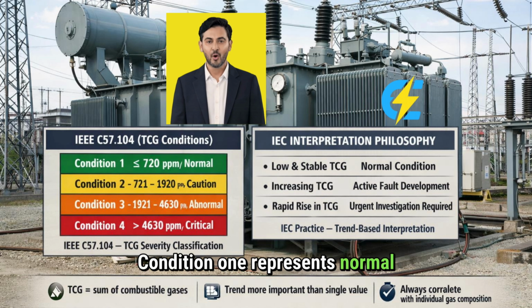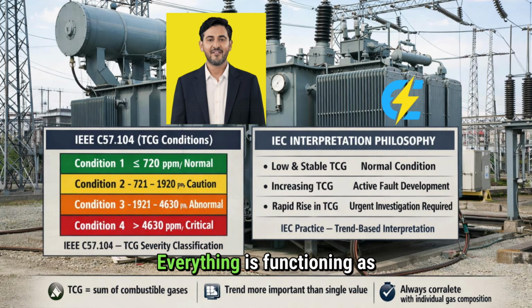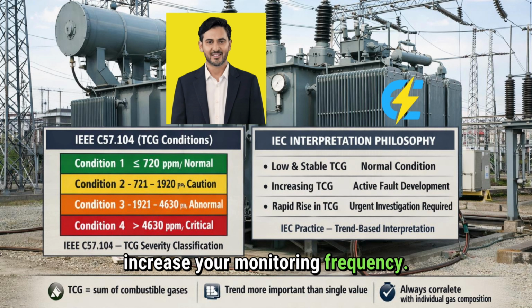Condition 1 represents normal operation with TCG below 720 parts per million. At this level, your transformer is operating satisfactorily and you can continue with routine monitoring. This is your green light. Everything is functioning as expected. Condition 2 covers the elevated range with TCG between 720 and 1920 parts per million. This indicates greater than normal combustible gas levels. You're not in immediate danger, but increased vigilance is required. Think of this as your yellow light. Proceed with caution and increase your monitoring frequency.